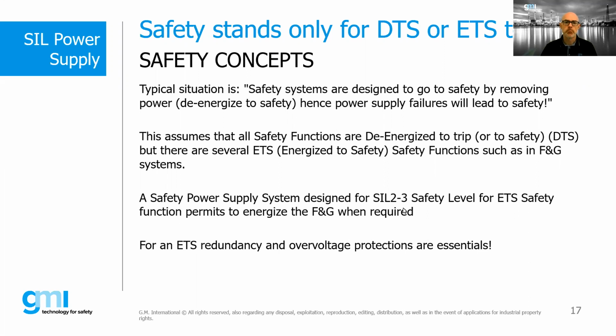Really, there are many applications where the safety function is to energize the load. Therefore, of the energized to safe or energized to trip type, as in a fire and gas system, a safety power supply is designed to guarantee a SIL2 or SIL3 safety level, also for energized to safe applications, which need to energize the load on request. Well, for this type of application, redundancy and overvoltage protection are essential.